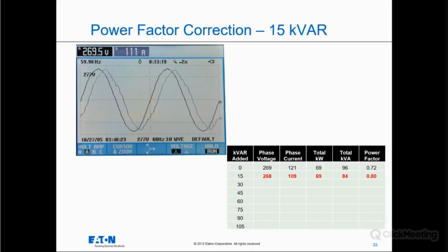We can see what happened. It dropped, which is what we would expect. Why did it drop? Because we're supplying a portion now of that reactive power from our capacitors. So we're supplying it locally and we're not pulling it from the utility. So as we add 15 kVAR increments, we can see this trend continuing, the phase current dropping, the kVA dropping, the power factor getting better.